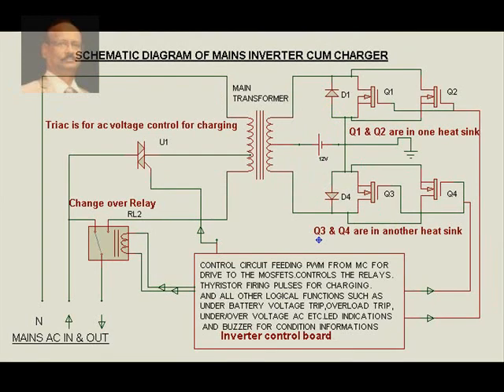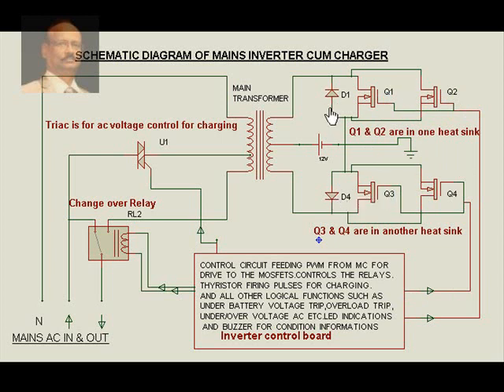It should be noted that during mains availability, the drive to the MOSFETs is not given — the drive coming from the control card is disabled. In the process, these MOSFETs are assumed to be non-existent. So the inbuilt diodes of the MOSFETs are present and they behave as rectifying diodes for battery charging purposes, as explained.